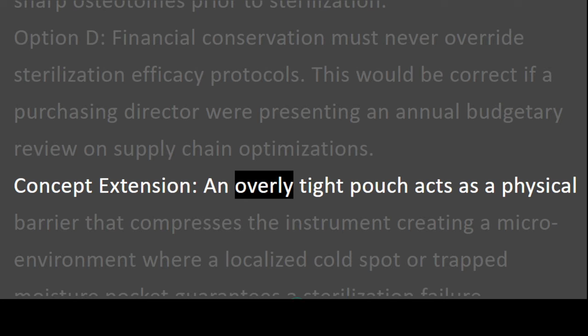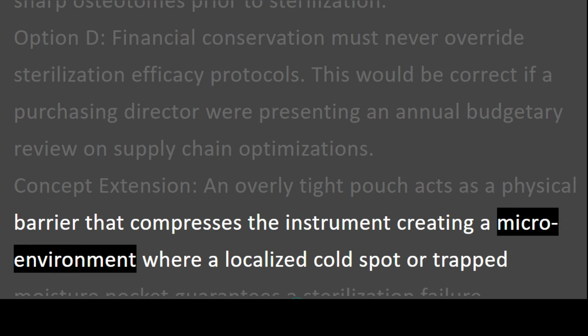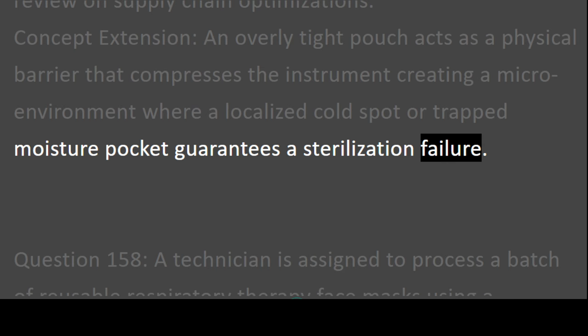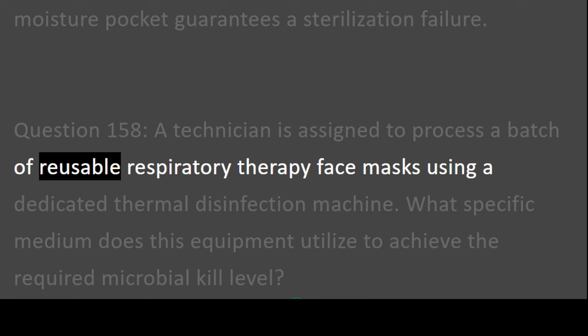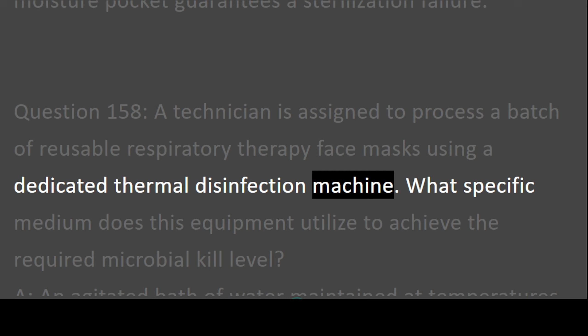Concept extension. An overly tight pouch acts as a physical barrier that compresses the instrument, creating a microenvironment where a localized cold spot or trapped moisture pocket guarantees a sterilization failure. Question 158. A technician is assigned to process a batch of reusable respiratory therapy face masks using a dedicated thermal disinfection machine.